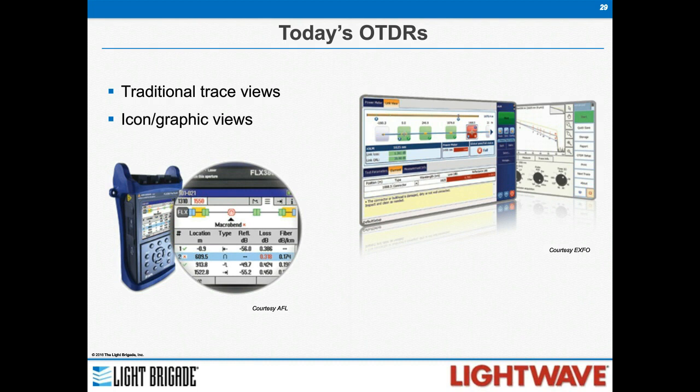But the feedback we get from field techs and from some of the supervisory personnel is that they really still want their techs to understand what an OTDR trace is about, what it shows you, what you can learn from your network by evaluating an OTDR trace. And when you're troubleshooting, sometimes it's better to look at that than some icons. So although this is very helpful for lower skilled techs and for getting some quick answers, it's not always the end-all be-all for everything you need. So as you're considering what to buy or what to use, think about the big picture. The icons are great and they can be very helpful, but they may not be the entire solution.